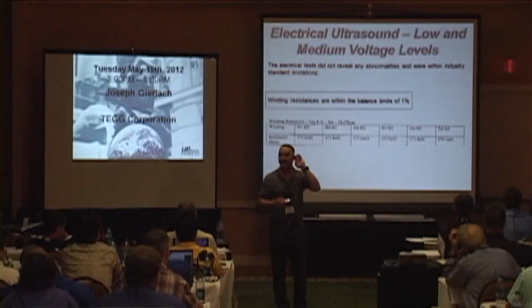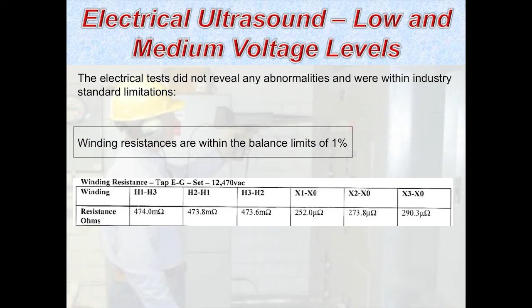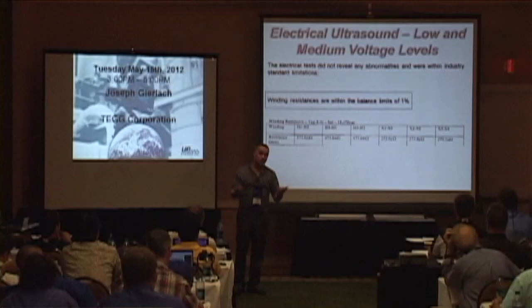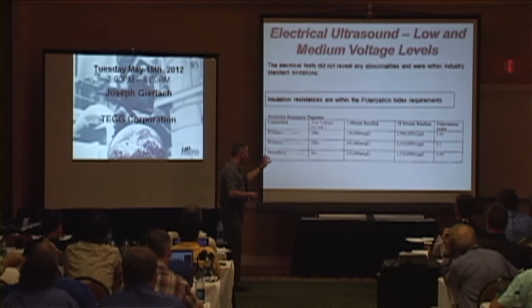So the winding resistance test, all you're looking for on this test is balance between the coils. They should be almost identical if it's constructed correctly. And they were within the 1% tolerance based on this data right here. So everything looked good there. This here indicates the insulation resistance test. And as I mentioned, this tells us how well the insulating system can contain the stresses. And remember, on the primary side is 12,000 volts, secondary is 480.